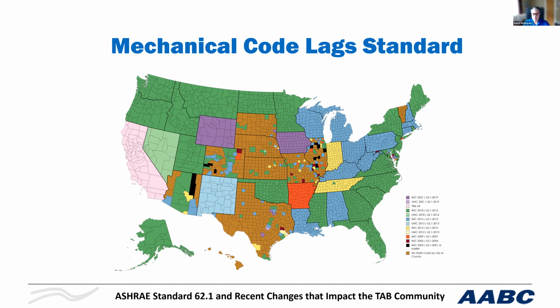And most of the states incorporate statewide, but there's a handful of states, about a dozen states, that incorporate per county or per municipality. And then some of the major cities in the US have their own ventilation code as well. One important thing to note is that the Uniform Mechanical Code or the International Mechanical Code do not incorporate 100% of 62.1. So keeping up to date with the latest of 62.1 helps ensure professional competency with indoor air quality, because we're constantly evolving the standard, adding new lessons learned, and improving upon what has been done in the past.